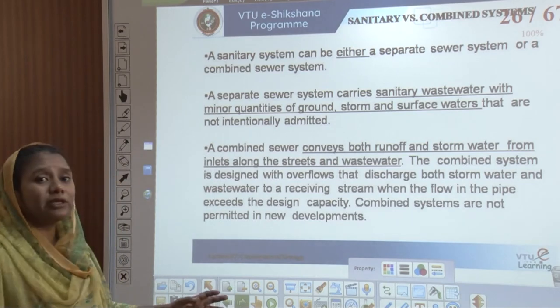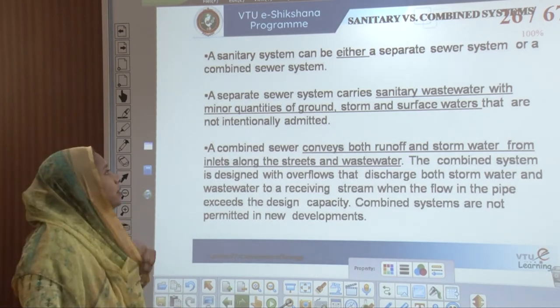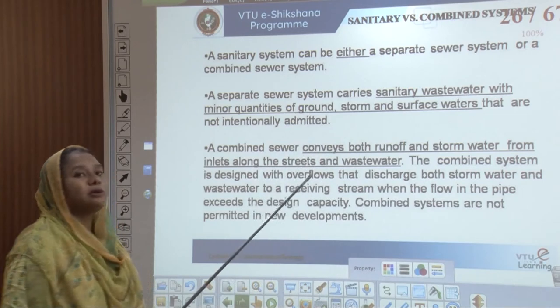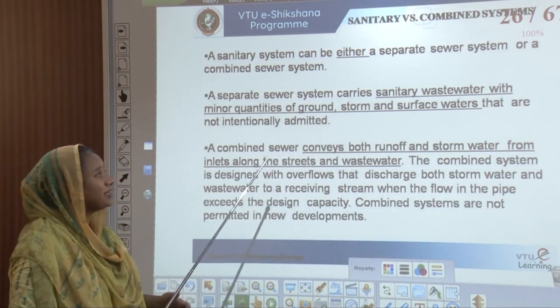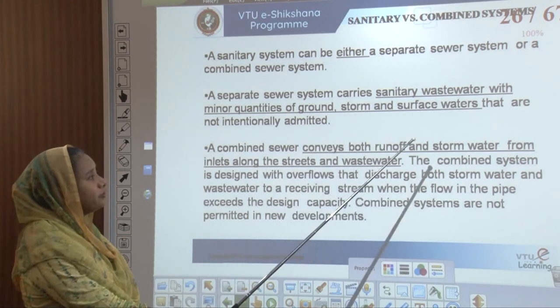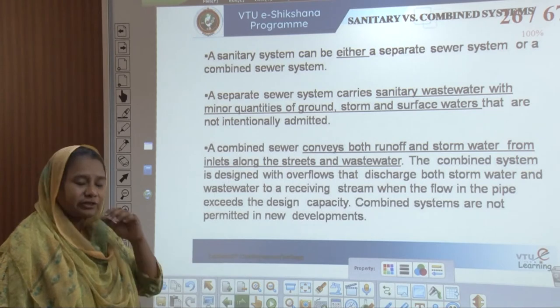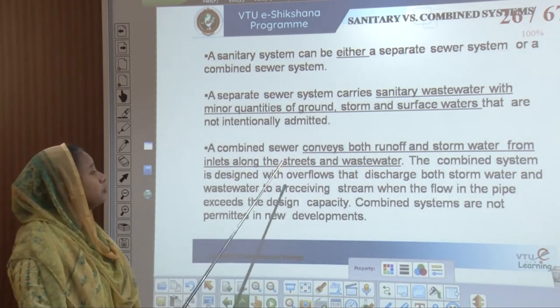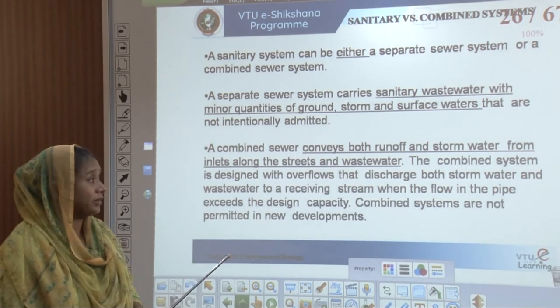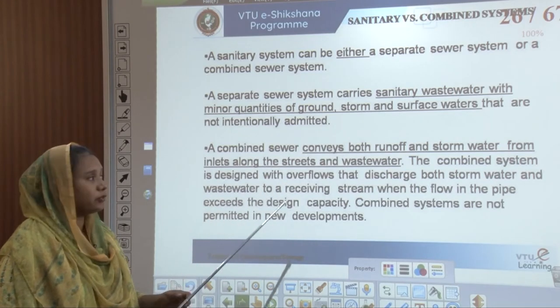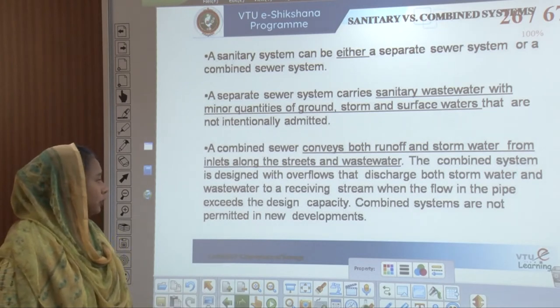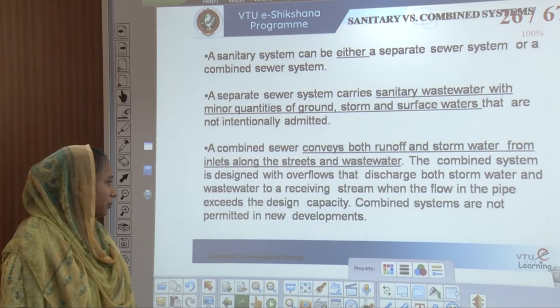Comparing sanitary and combined systems: a separate sewer system carries only sanitary wastewater with minor quantities of ground and surface water not intentionally admitted. In a combined sewer, both runoff and storm water from inlets along the streets and wastewater are put together. The combined system is designed with an overflow that discharges both storm water and wastewater to a receiving stream when flow in the pipeline exceeds the design capacity.